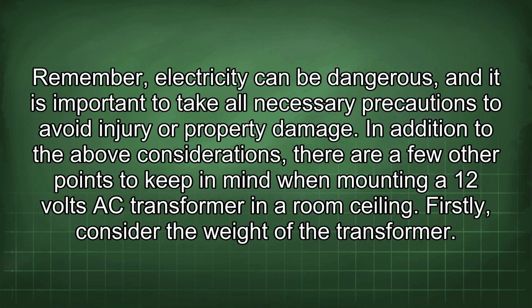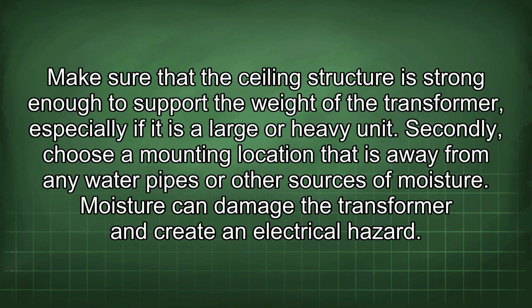In addition to the above considerations, there are a few other points to keep in mind when mounting a 12-volt AC transformer in a room ceiling. Firstly, consider the weight of the transformer. Make sure that the ceiling structure is strong enough to support the weight of the transformer, especially if it is a large or heavy unit. Secondly, choose a mounting location that is away from any water pipes or other sources of moisture. Moisture can damage the transformer and create an electrical hazard.